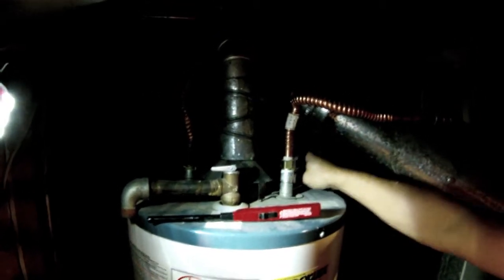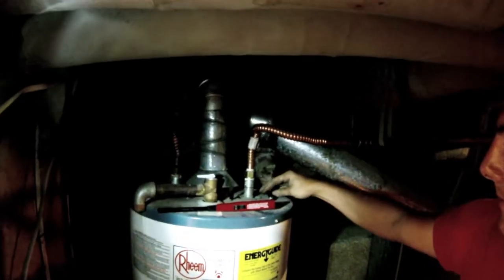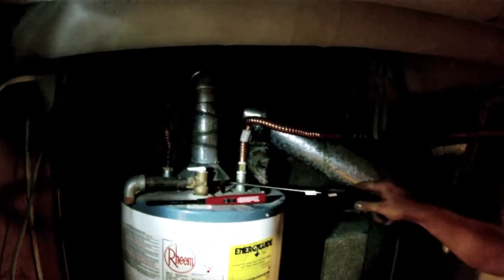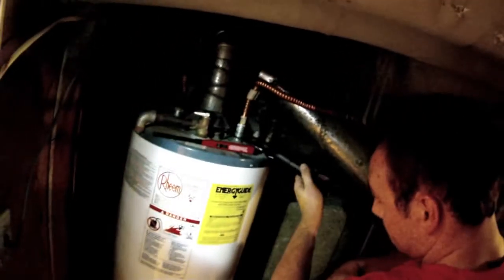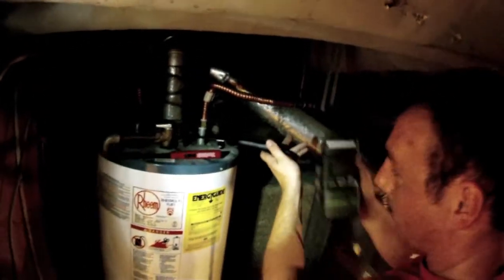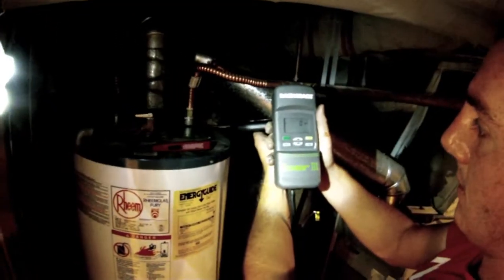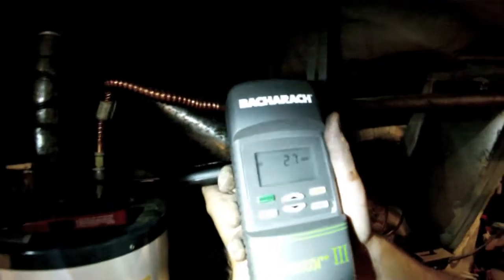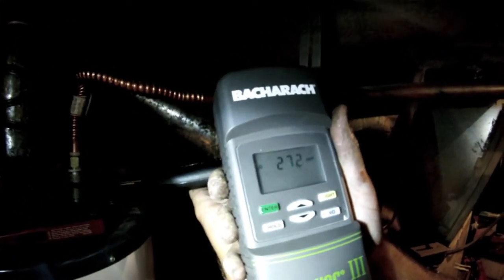So the gas is there, and what I'm really concerned with is the parts per million. Then in the porthole — just watch this baby skyrocket. Anything above 100 automatically fails. This machine is not working. It's unsafe. I'm going to turn it off.